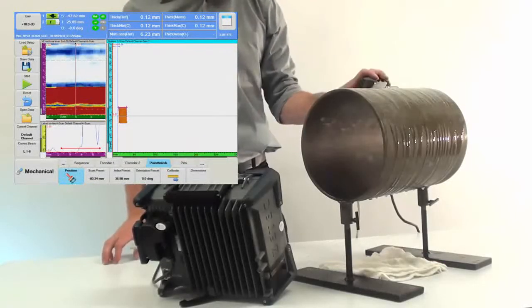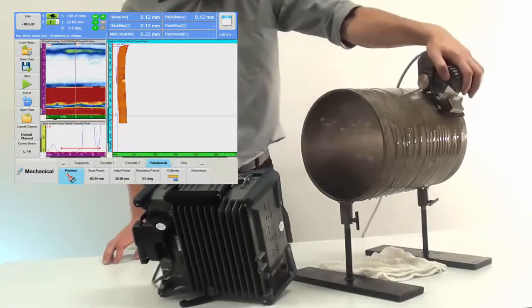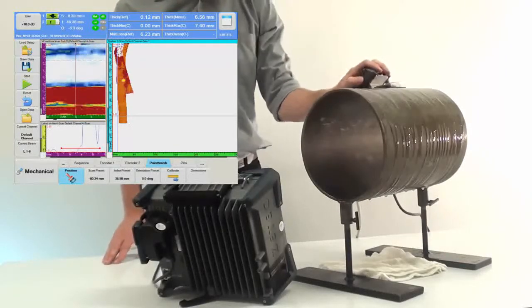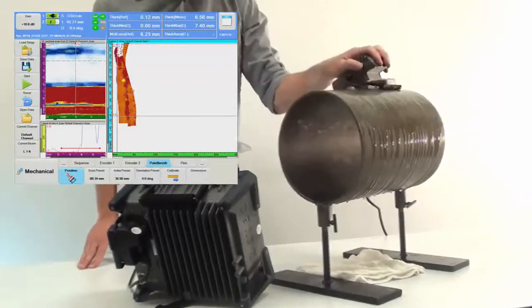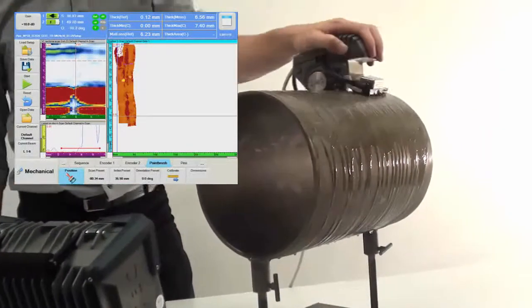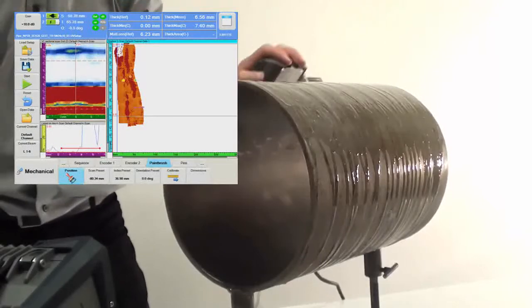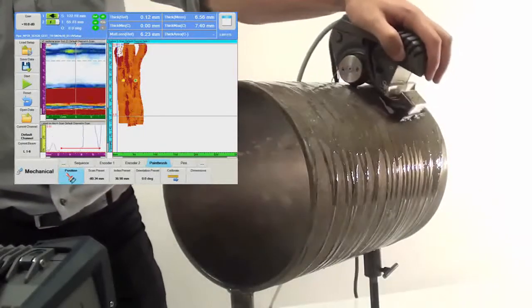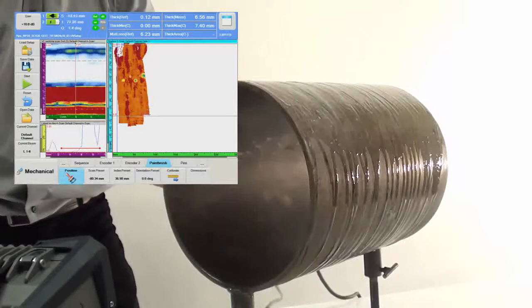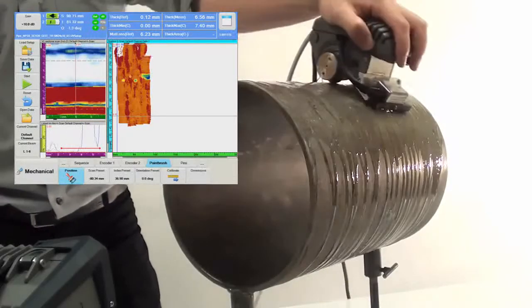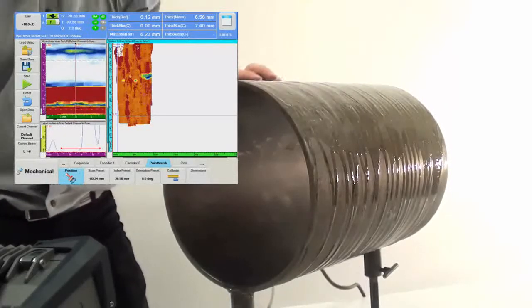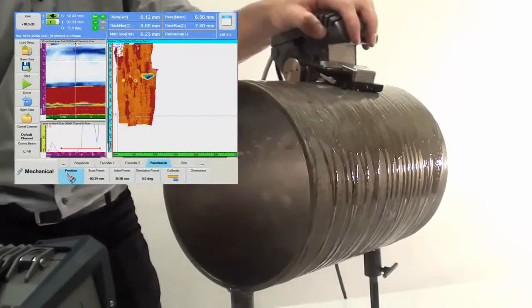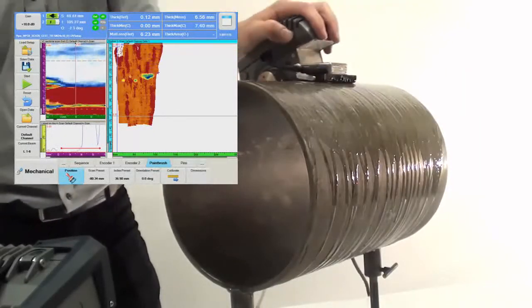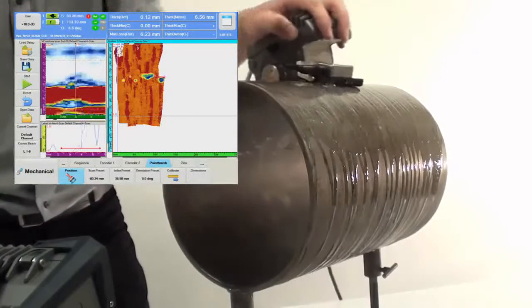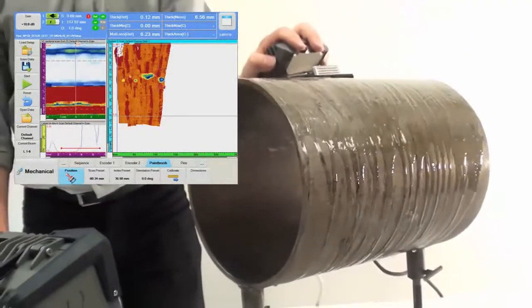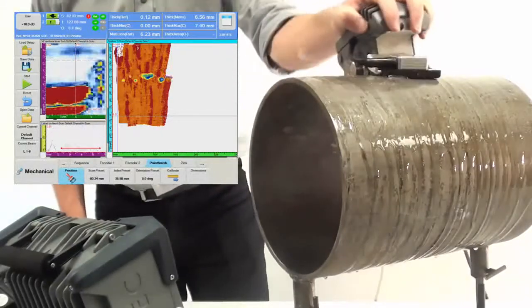Upon touching the reset button, the C-scan view shows the actual position of the paintbrush wheels, and data recording can start. As soon as NDT paintbrush is moved over the pipe surface, the system accurately tracks the position and orientation of the probe while allowing for a free movement of the probe. The corresponding phased array UT signals are displayed on the TOPAZ16 screen in real time. Data from the successive strokes is accurately positioned on the scanning surface, and the covered area can be easily monitored on the C-scan view.